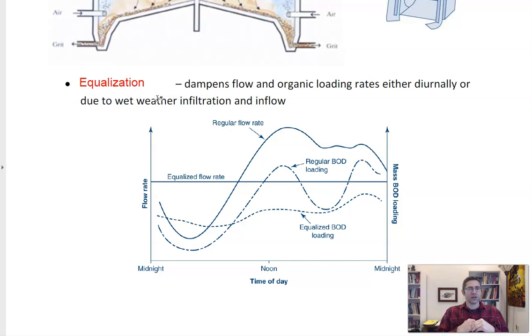Other facilities like Newburgh, you might have large treatment processes downstream, like your secondary process. They have these large oxidation ditches which can just basically fill up with more water, and so they serve almost as an equalization.